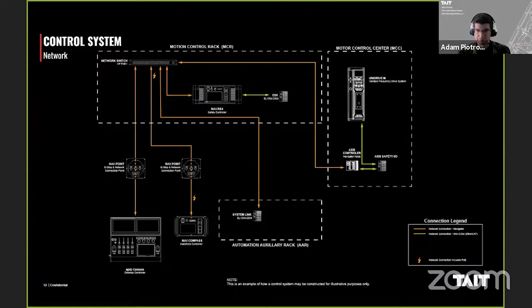It's going to talk via field bus to the IO pieces, and via field bus to the drive itself to do the motor control. This is a lot better than running discrete wires for the drive enable, the drive set point, the drive brake release. The list could go on and on in terms of the IO signals you may need to a drive, or you just run a network cable and it talks via that.